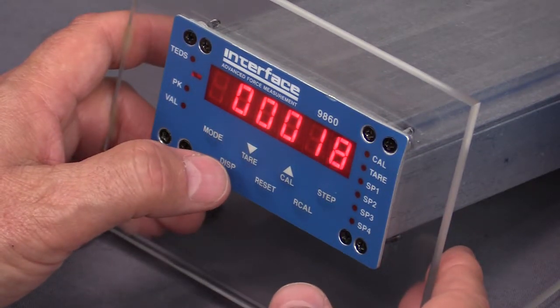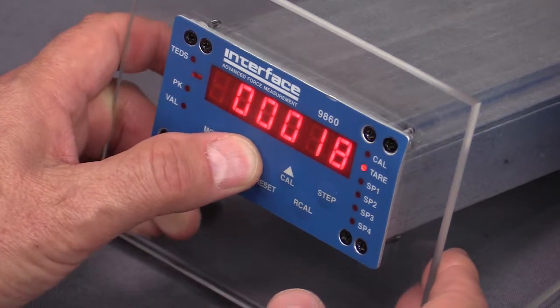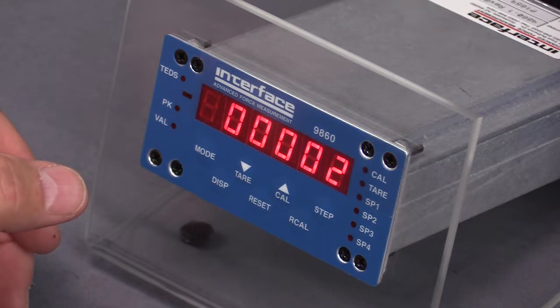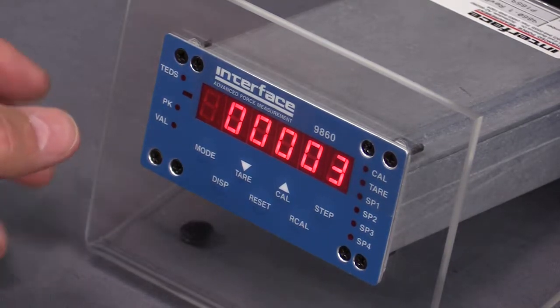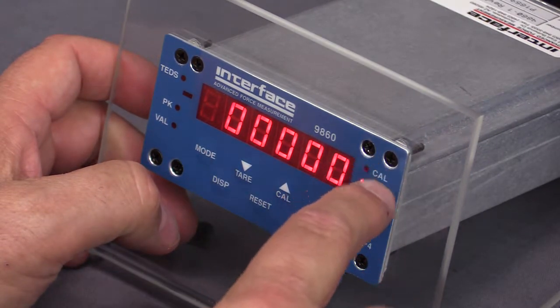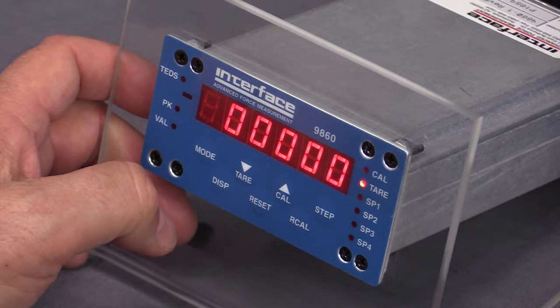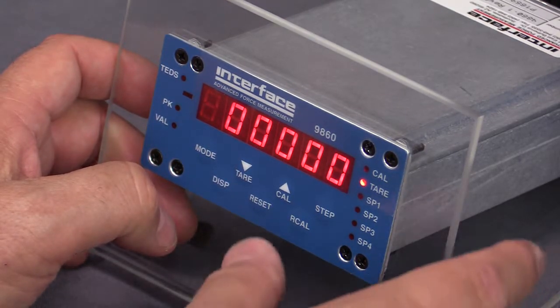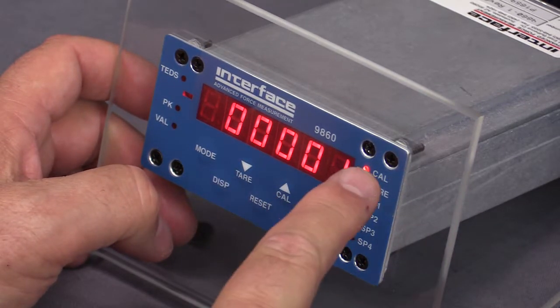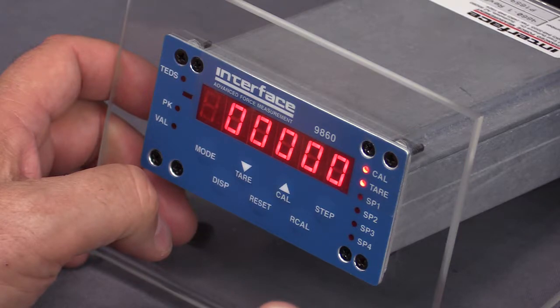Now we're going to do the actual calibration. The first thing we're going to do is press the tare button. When we do that, tare illuminates and the display goes to zero. The next thing we're going to do is press the cal button. The cal light comes on and now we've entered into the cal mode. We're ready now to apply our load. We're going to do that by using the CX transfer box.